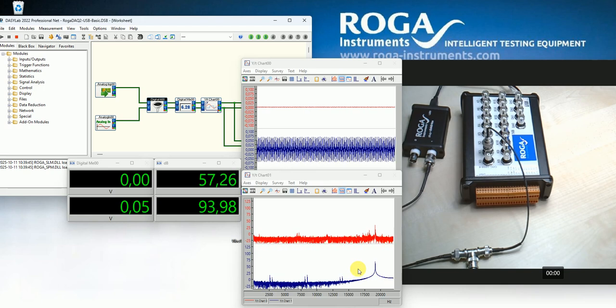It is only not as linear anymore as before. Because it is specified, let's say, from 5 Hertz to 20 kilohertz, but the sensor still gets some data above 20 kilohertz. So in many cases, the effect is that you measure signals above the Nyquist frequency, which are mirrored down to the lower frequency bands.